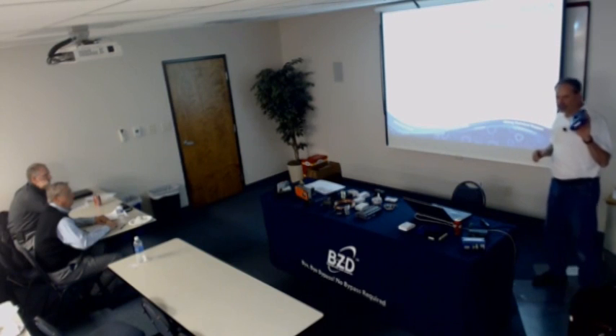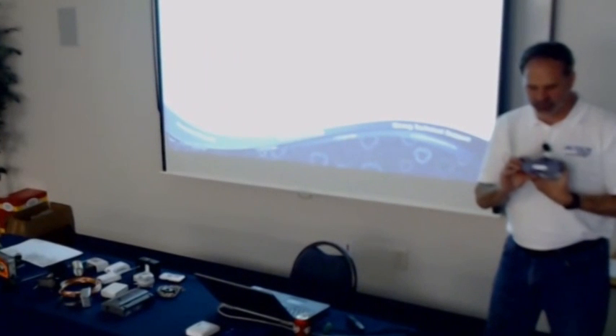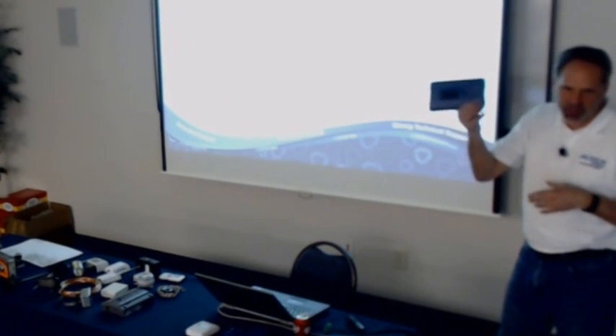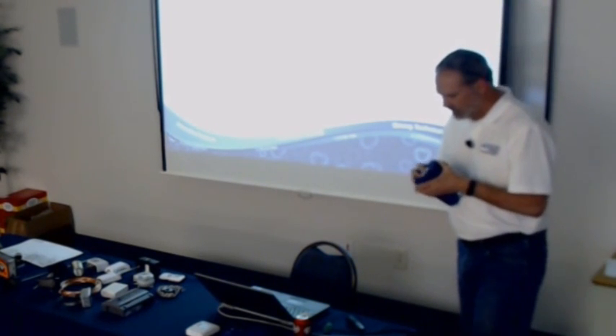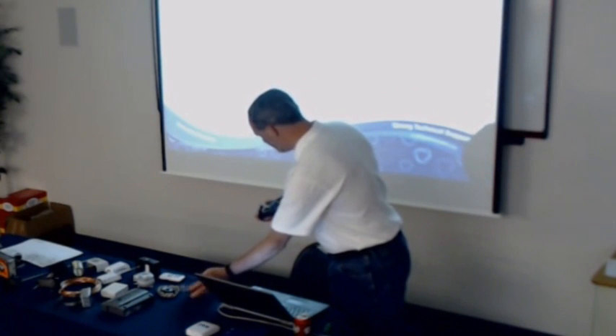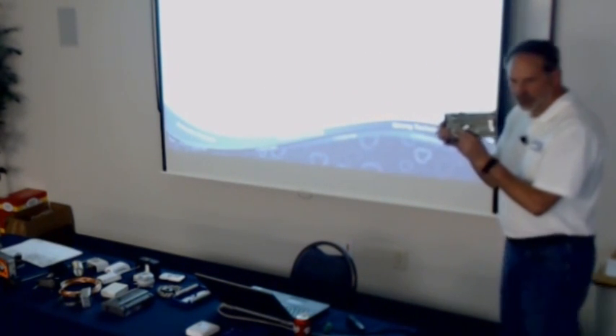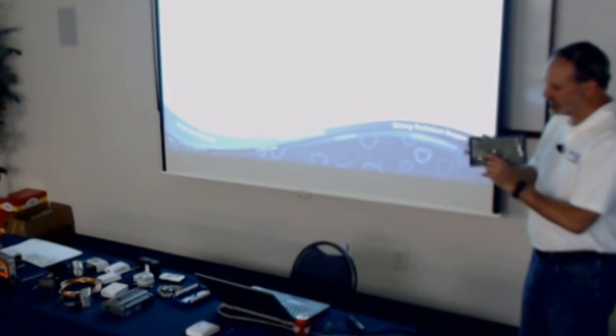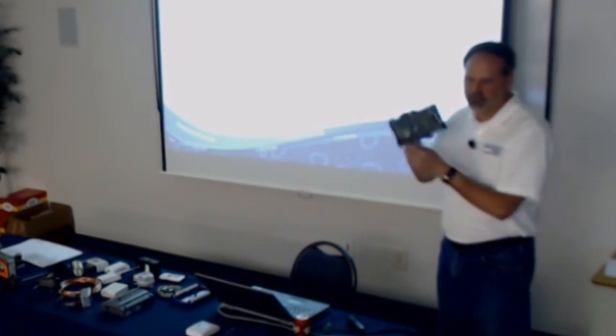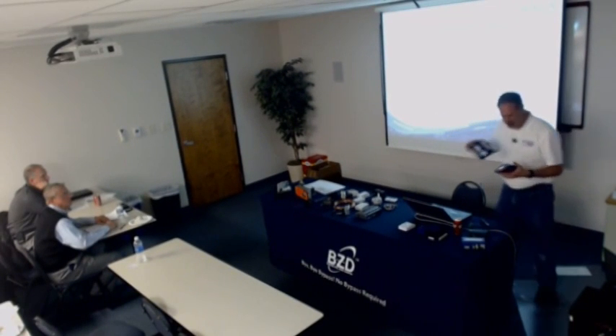Distech makes all of their controllers in both BACnet and Lon. They look identical except for this one. This one happens to be Lon, and it's got the little Echelon certification here. If it was BACnet, it'd have the BACnet certification here. And the only thing that's different inside is the little communication card, which is this guy right here, and it even says Echelon, which is the people who make Lon. You could actually pull this out, stick a BACnet card in there, and it's the same piece of hardware. At least for Distech, they program identical. They look and act identical, and there's very, very little difference between the two.